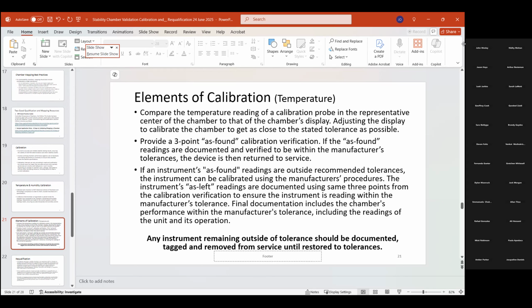And the big thing here: any instrument remaining outside of tolerance should be documented, tagged, and removed from service until restored to tolerances. In the good old days, we just simply had a few tags on there. If you walked around and inspected the tags, you could make sure that you were always within the time period. These days, there's calendars, bells, whistles, warnings. Nobody should actually miss a calibration interval because of all the great reminders that can be with the maintenance people, with the stability people. All over the place, there should be bells and whistles saying you've got so many days left. And then the whistles get a little louder the closer you get to your deadline without recalibrating.